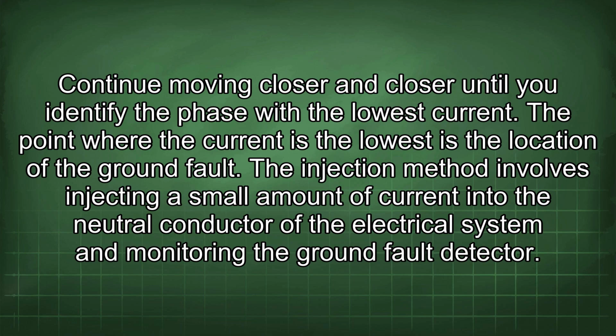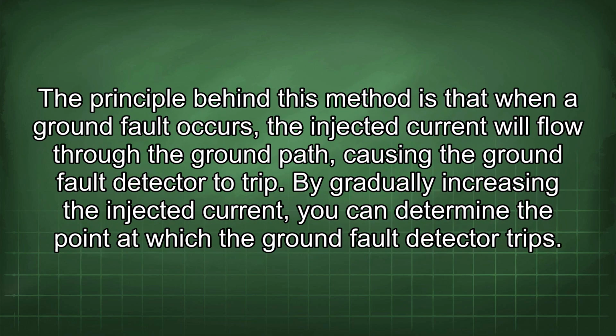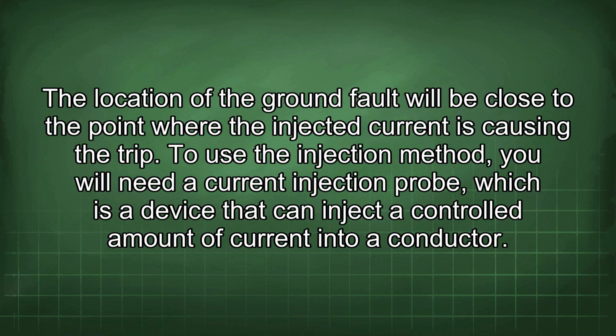The injection method involves injecting a small amount of current into the neutral conductor of the electrical system and monitoring the ground fault detector. The principle behind this method is that when a ground fault occurs, the injected current will flow through the ground path, causing the ground fault detector to trip. By gradually increasing the injected current, you can determine the point at which the ground fault detector trips. The location of the ground fault will be close to the point where the injected current is causing the trip.